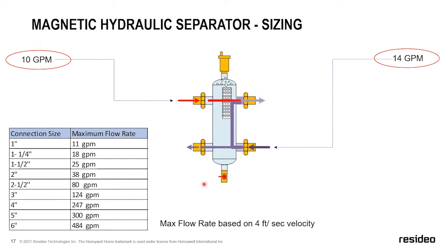You've got two ways of looking at it. One, assuming your system was designed properly, just go off the larger of whichever pipes you're connecting to. So if we have 1 inch here, 1.25 inches over here, you're going to use a 1.25 inch hydraulic separator. If you want to use these different flow rates, feel free to use this as a point of reference. These are very conservative flow rates. I never designed a system for more than 14 gallons a minute on 1.25 inch pipe, but here are some recommendations on the maximum flow rate to keep this consistent.